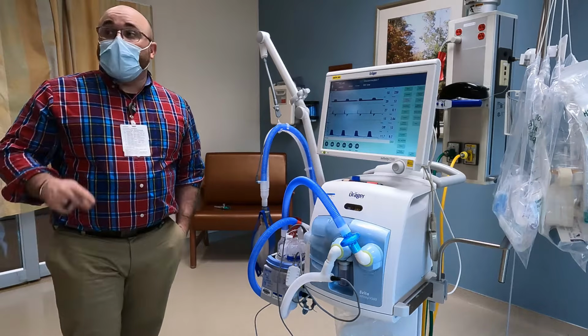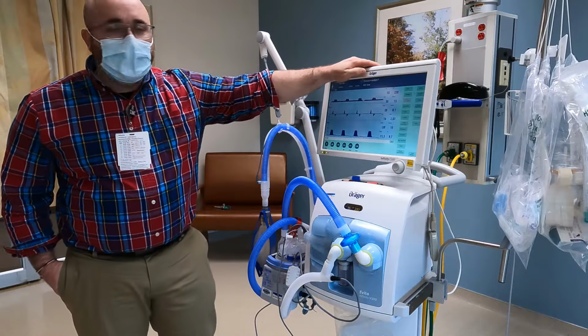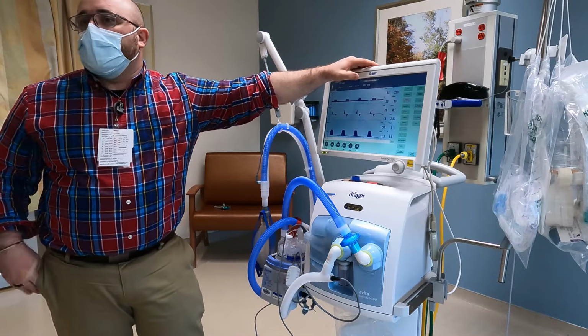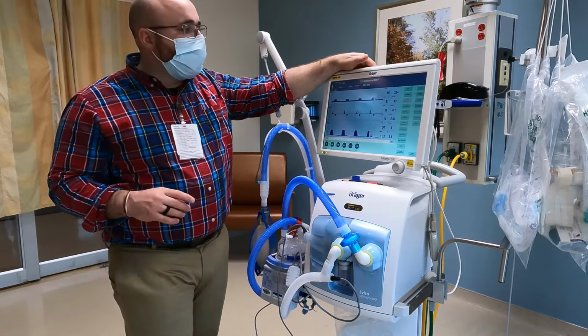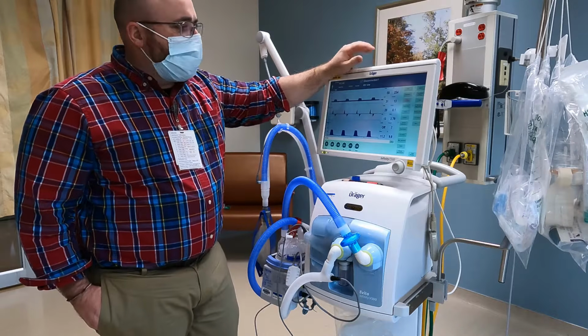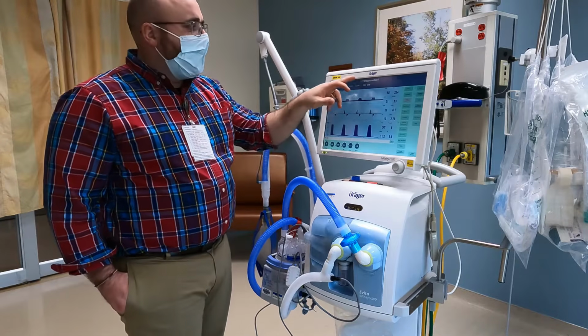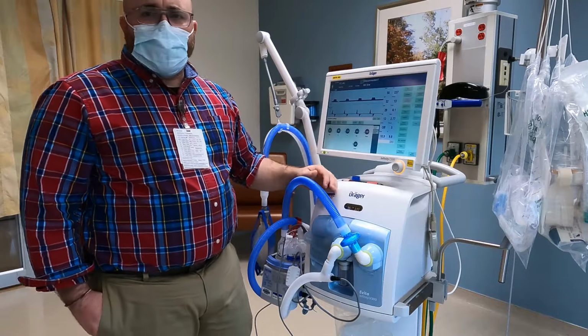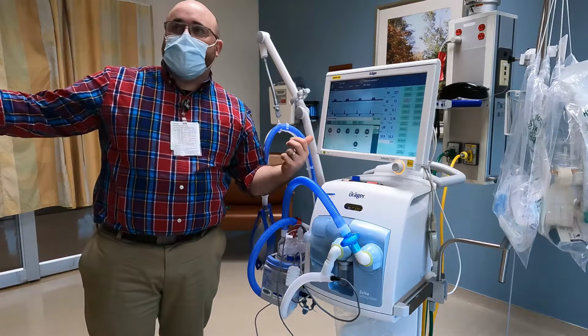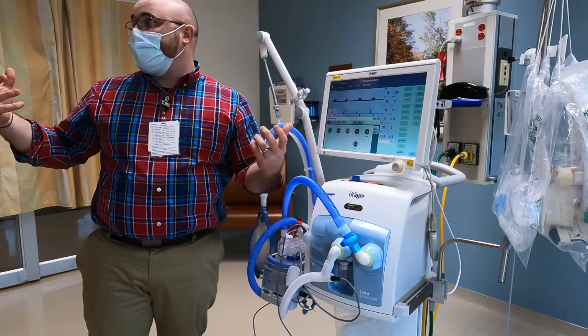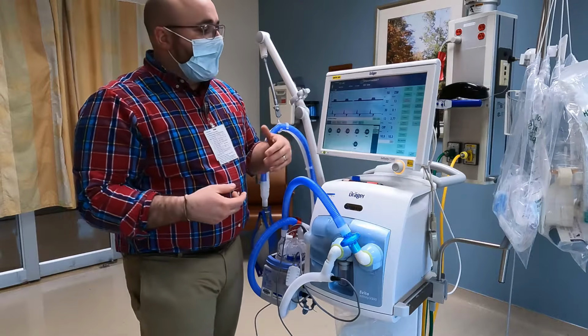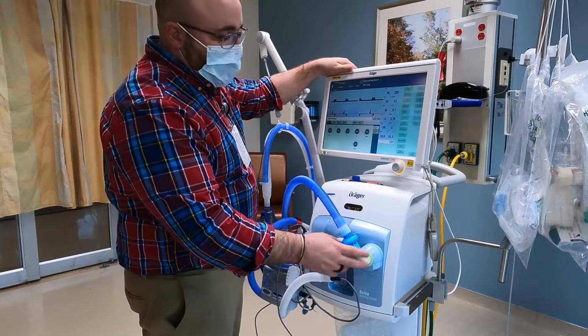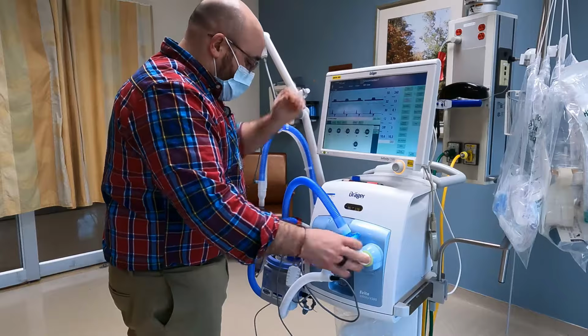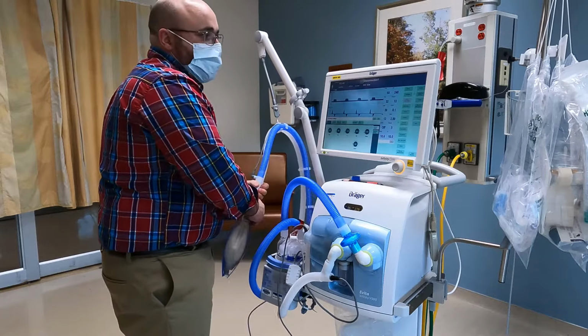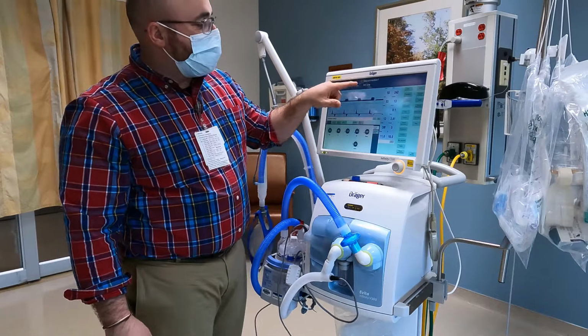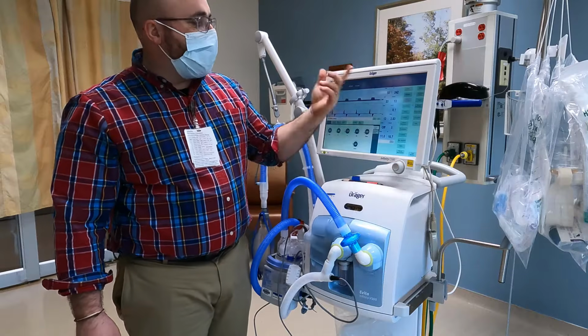Every red alarm or yellow alarm will be right here. This is in the alarm history. If you come in and you say, low minute ventilation, disconnection, I mean, okay, we're good now. You know, you might think, disconnection, why'd that happen? Well, maybe the RT suctioned or something. When you suction, it thinks it's disconnected because you're pulling the air away. So maybe they suctioned and didn't use the right button. Or you could also just check connections, like, did something pop off here? Because I don't want it to do it again. So then you just touch it, confirm it, and it clears the top.